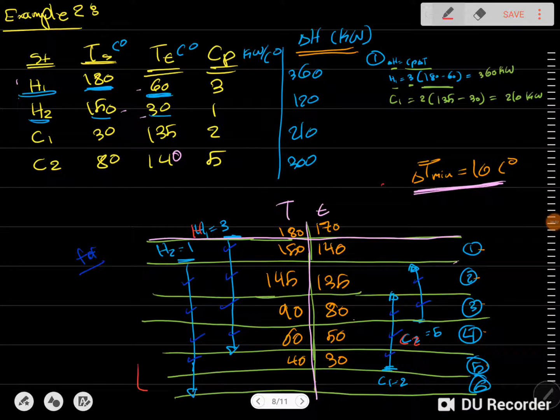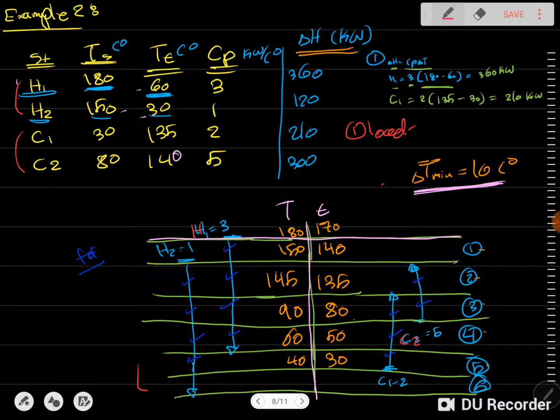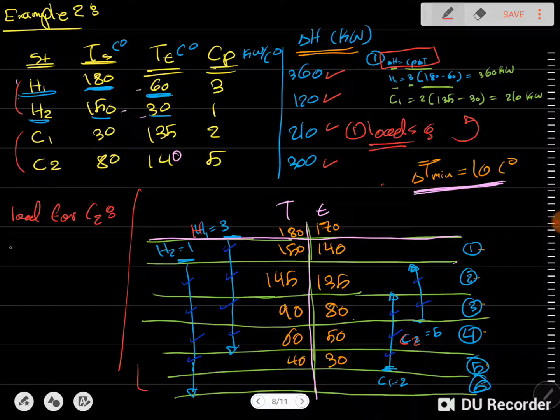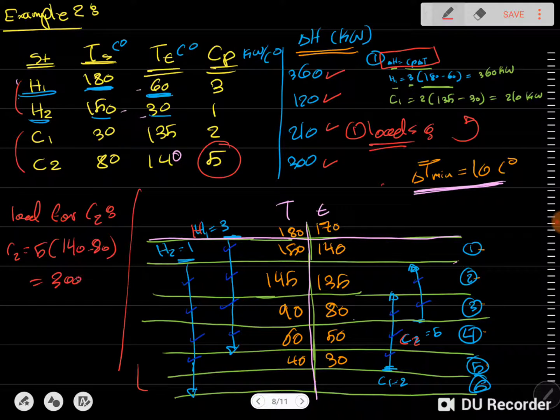We have a problem with two hot streams and two cold streams. The first step was to calculate the load, which I found using ΔH = CP·ΔT. For example, the load for C2 equals CP 5 multiplied by 140 minus 80, which gives you 300 kilowatts. We follow this method to find all the other values.